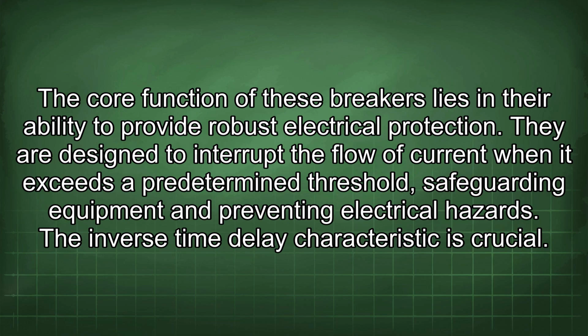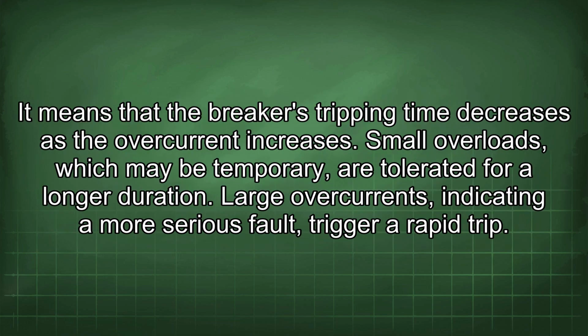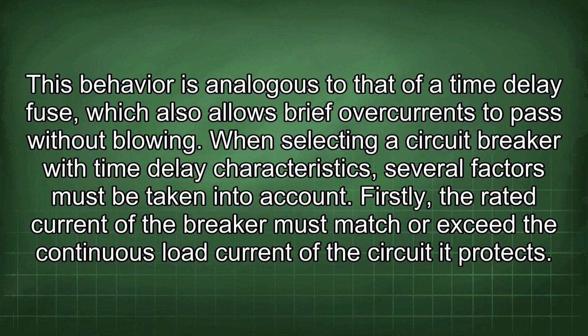The core function of these breakers lies in their ability to provide robust electrical protection. They are designed to interrupt the flow of current when it exceeds a predetermined threshold, safeguarding equipment and preventing electrical hazards. The inverse time delay characteristic is crucial. It means that the breaker's tripping time decreases as the overcurrent increases. Small overloads, which may be temporary, are tolerated for a longer duration. Large overcurrents, indicating a more serious fault, trigger a rapid trip. This behavior is analogous to that of a time delay fuse, which also allows brief overcurrents to pass without blowing.